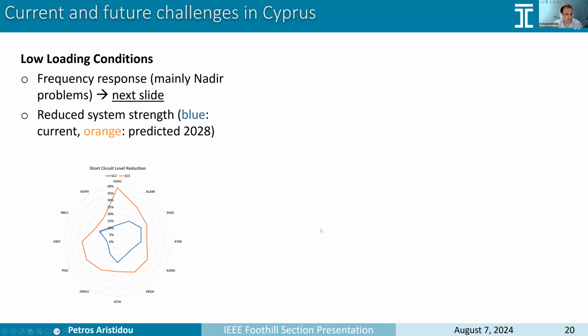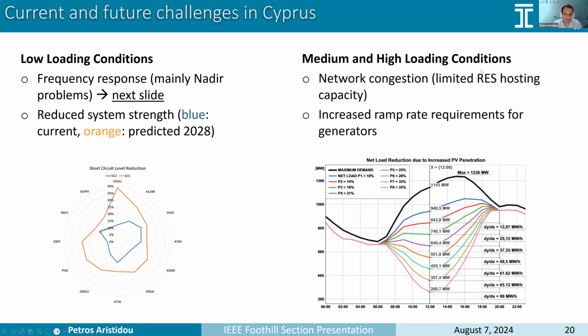But that's not only the case in low loading conditions. Even in medium and high loading conditions, we have lots of problems related to network congestion. So that creates limits in the renewable energy sources hosting capacity. And we also have problems related to the ramp rate requirements of the generators. For example, here we can see different penetration levels. This was taken again from the control center. And we can see that at different penetration levels, the ramp rate required by the conventional units to take on the load in the afternoon goes from 20.9 megawatt per hour to 86 megawatt per hour when we reach 35% here.